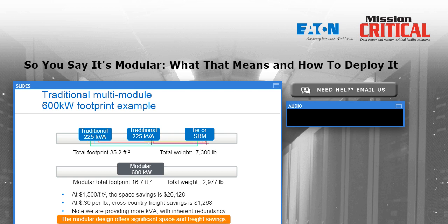So there are some significant savings on day one when I put this thing in: footprint and upfront cost. There's also savings in total cost of ownership. If I have 2 UPS systems and 2 battery systems, I'm going to need a maintenance contract for each of the UPS systems and another maintenance contract for each of the 2 battery systems. Now, they're co-located on the same site, so the price should be reasonable for that, but certainly not as inexpensive as having one maintenance contract for my modular UPS and one for my single battery system. So over the 15 to 20-year service life of the machine, I would end up having a significantly lower total cost of ownership.